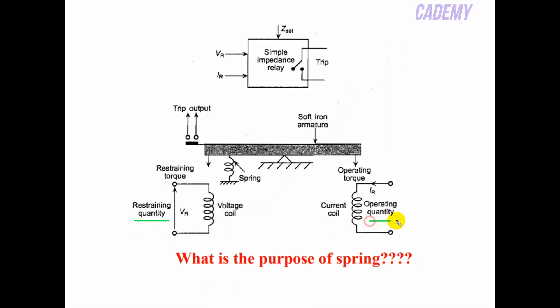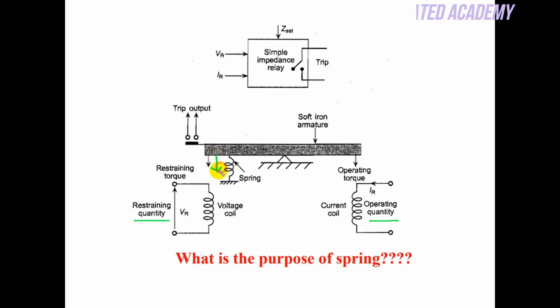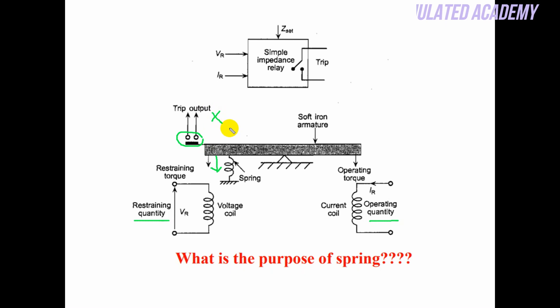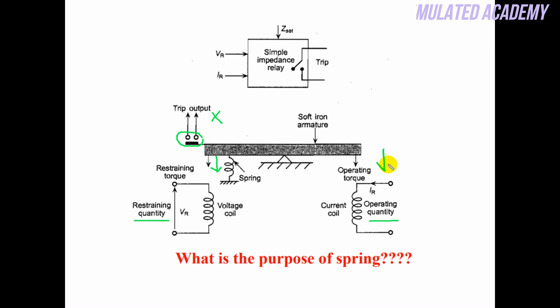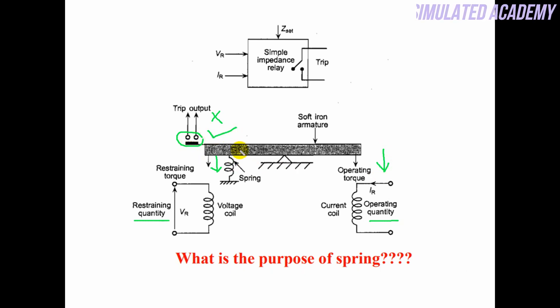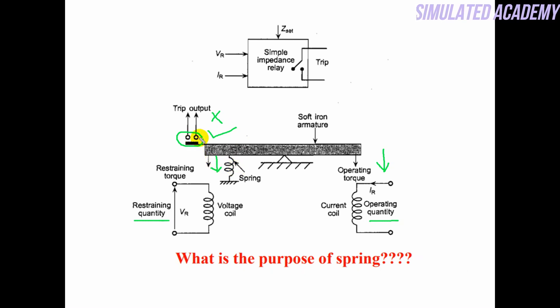If the restraining torque is greater, it will attract the beam downward, so the contact will not close and no trip signal will be generated. If the operating torque is greater, it will attract the beam downwards, the contact will close and a trip signal will be generated. The spring is used to ensure that under normal conditions the contact does not close and no trip signal is generated.